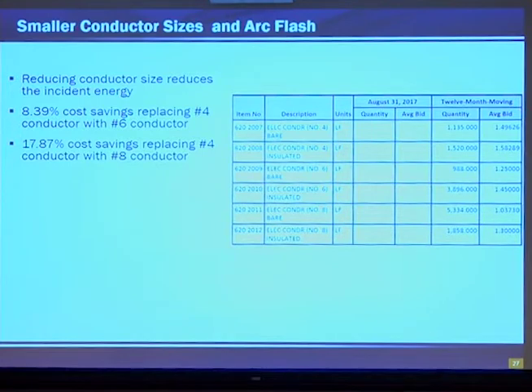Reducing conductor size is reducing the incident energy, but is there anything else that can help with? These are just the rolling costs. It reduces money as well. There's cost savings. There's an 8.39% cost savings going from a 4 to a 6. A 4 to an 8 is a 17.87% cost savings.